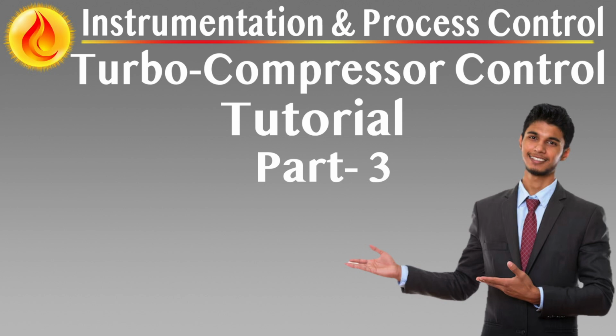Capacity performance control. The TCCS provides plant-level capacity control to align compressor performance with process demand. This controller resides in the CCP and operates in conjunction with the load-sharing and anti-surge subsystems to balance throughput, pressure, and machine integrity. Core objectives of capacity performance control: maintain plant suction or discharge pressure.